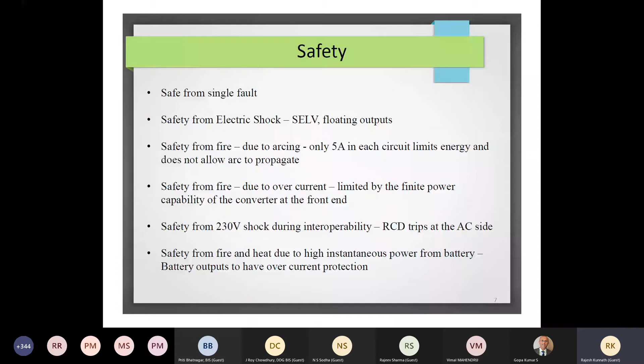From a technical perspective, what we call this system is an IT system. This is in contrast to the DC distribution, which uses a TT system. It's essentially an isolated system. This system of grounding is not different from what IEC has already included in their standards. If you look at IEC 60364-1, this is very well illustrated.